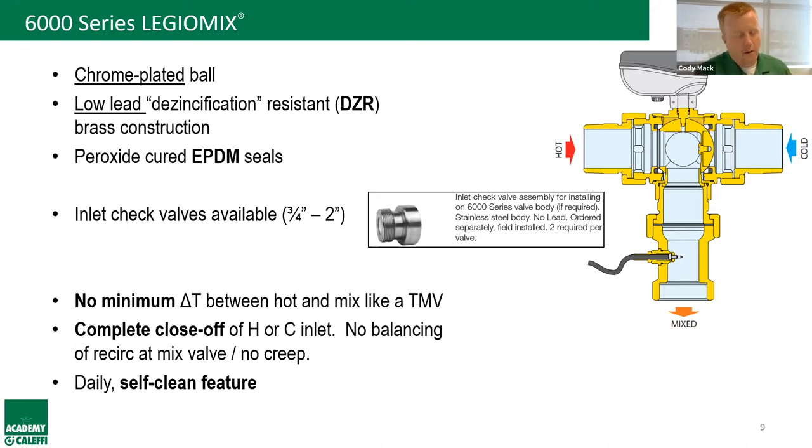We have a great Coffee with Caleffi webinar about recirc creep with Julius Polanco — one of our most popular. Another great feature is anti-clog: once a day, at 3 a.m. by default, the valve does a full rotation of the ball in both directions. This self-cleaning feature prevents scaling and seizing by using the seals to scrub the ball as it sweeps — it's on by default but can be disabled.